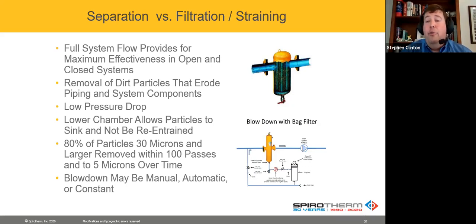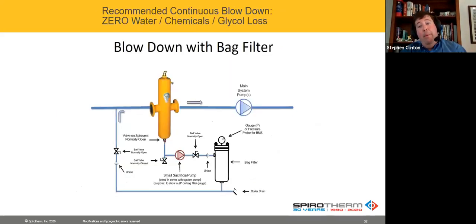Every unit that has dirt removal capability has a manual ball valve, but we recommend an automatic or maybe a constant blow down. I really like this approach, especially if you're looking at a unit that's maybe 12 inches or larger, especially the bigger units. When you blow the water down, you have to make up the water and chemicals and things like that. This is a system where you take a very small fractional horsepower motor and pump through a single sleeve bag filter, and the water continually flows through the unit. It's great because it is truly a closed system.